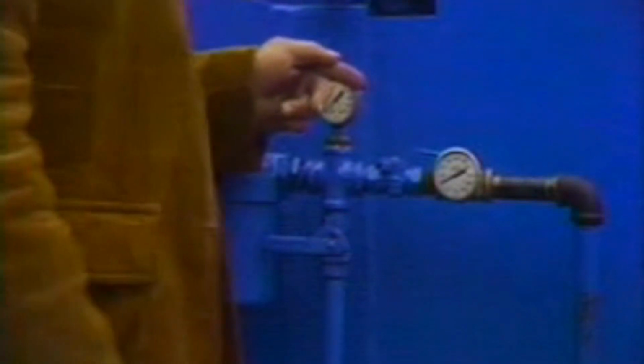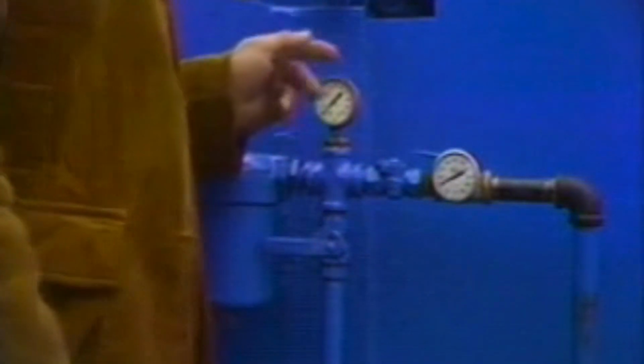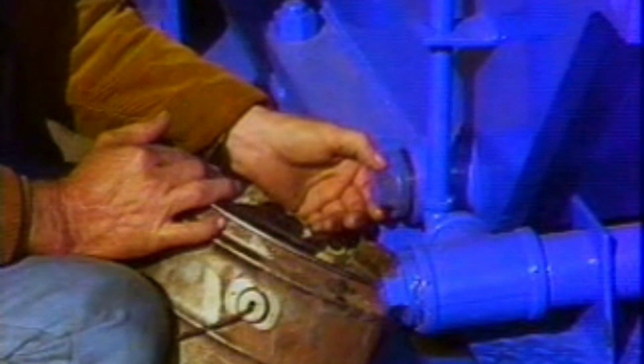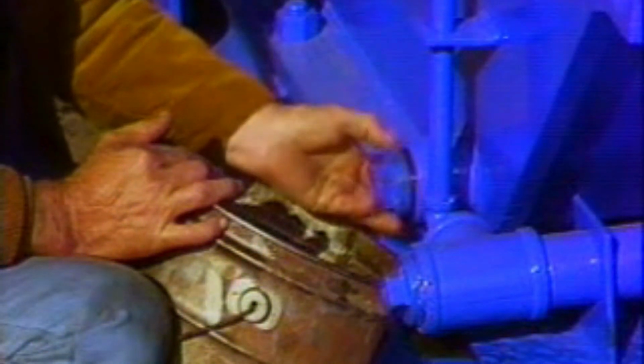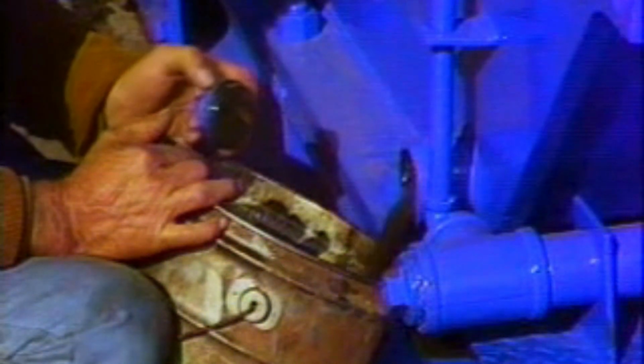Start the oil pump before the main pump. Make sure the oil temperature is okay. After running the main pump a few minutes, shut it down and check the oil level and add or drain as necessary. Now let's watch how it's done. Always be sure the pump is turned off and can't be accidentally started. Drain the oil from the crankcase.